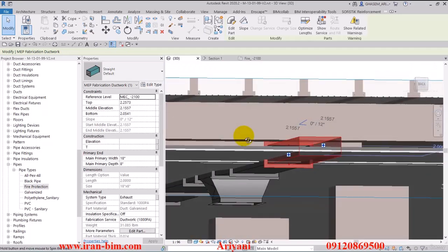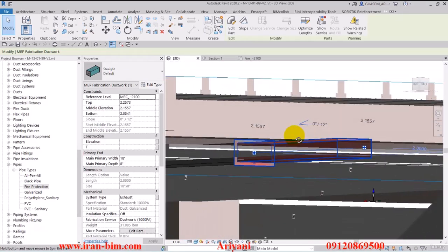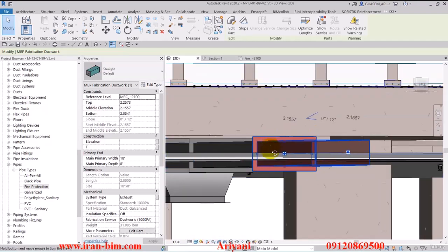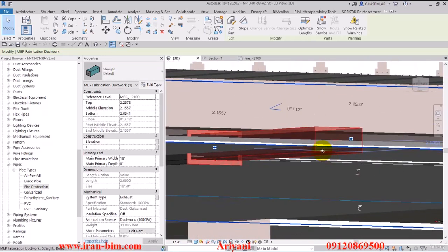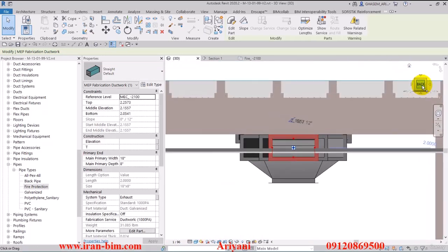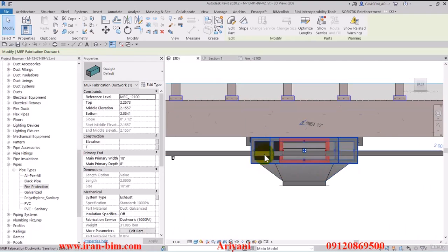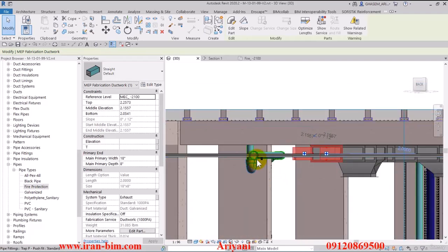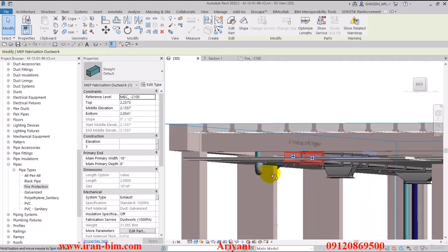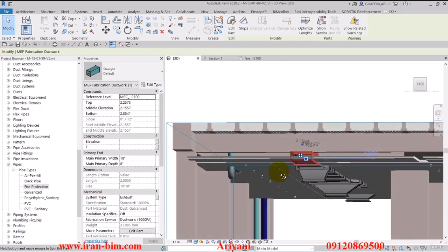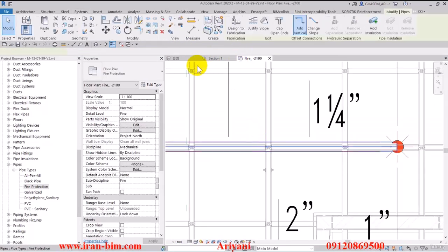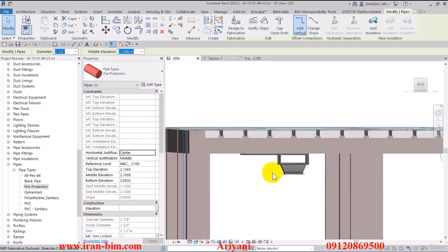So now if you look at the structure here, you can see we have the beam up top here, and so there's no more space to work with. Now we may have the unilet space on the side, which allows us to move this higher up for about a couple of centimeters and get rid of the issue easily. But if not, we may have to remove the suspended ceiling, or we'll have to create an architecture design where we change levels in the suspended ceiling itself. And the sewage pipe here, which is protruding through the ceiling, needs to be changed later on and adjusted using the consultation of the designer.